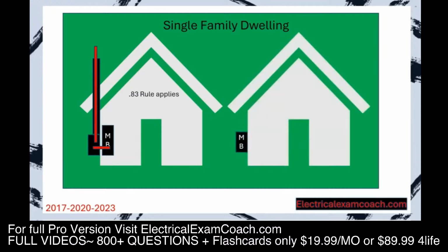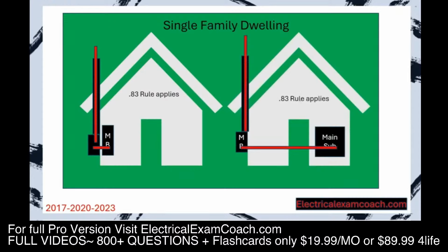Now let's imagine that we have a main breaker outside, we have the service riser, and we have a main sub panel inside. We have the riser wire and the wire going inside. The 83% rule applies to all this wire. You can apply it to the wire going up the riser, and you can apply it from the meter disconnect combo to the first main sub panel. Now the rule with this is that it has to be the panel that feeds the entire structure. You're not allowed to use it on other sub panels or on any sub panel that does not feed the entire structure. You have to be very careful with that one.